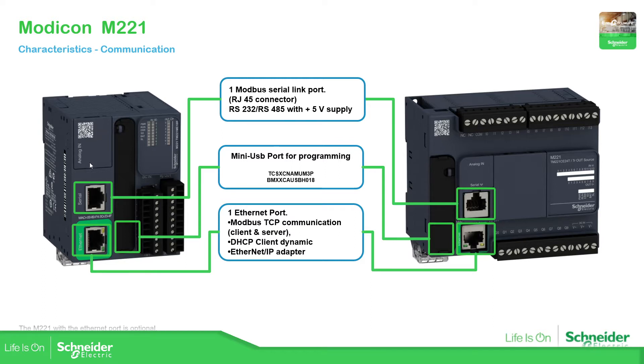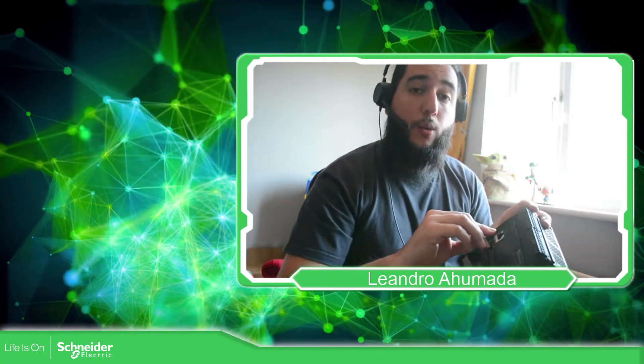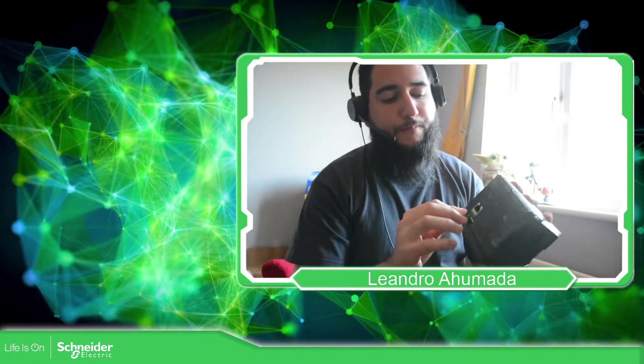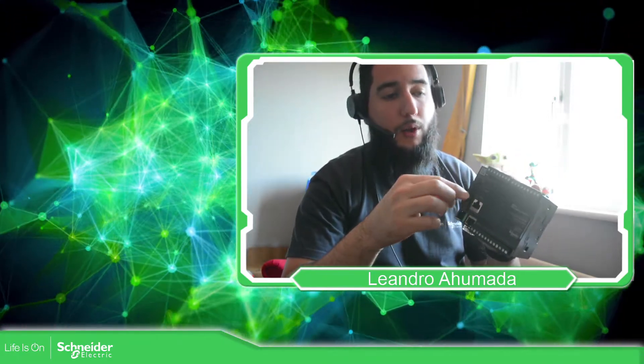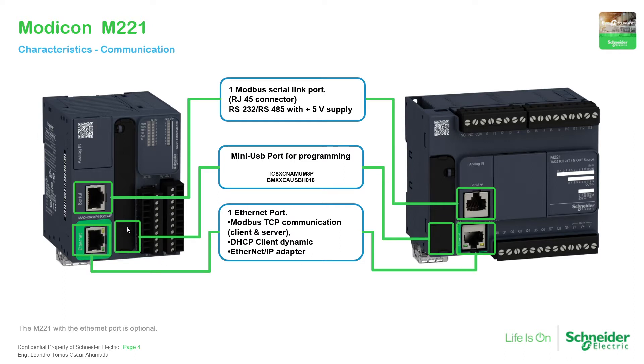Both the book and standard versions come with Modbus serial, but in the particular case of the book version, if you don't have the Ethernet port, it comes with two Modbus serial ports — that is one difference between the two models. There is also a mini USB communication port; you can see it at the bottom of the PLC once you remove the cover, which is used to connect to the PLC.